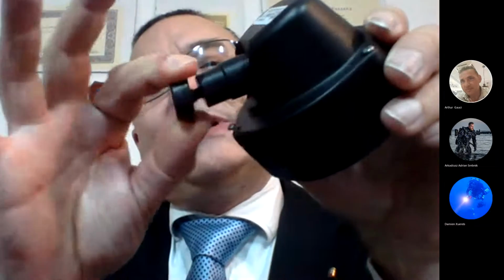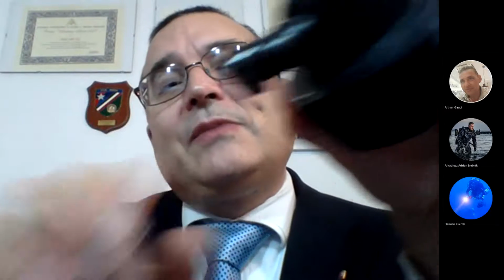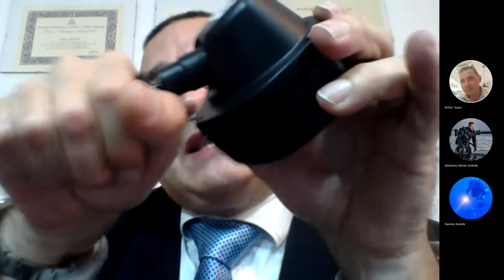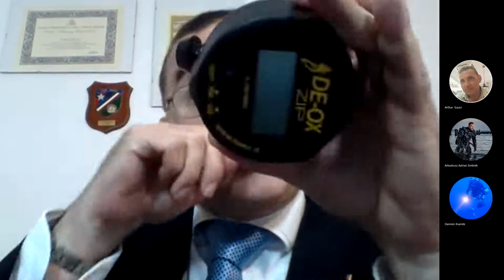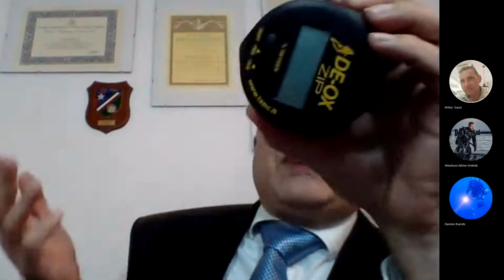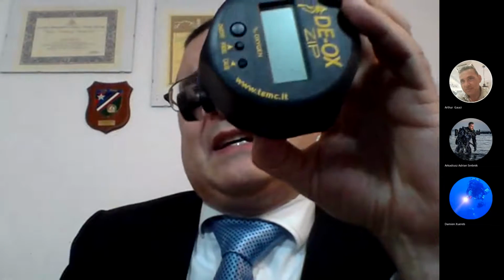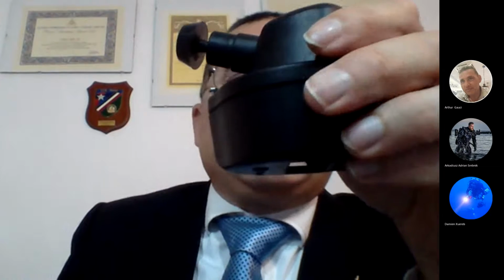So, okay, what is necessary for the analysis? Generally, the easiest way is to use the rubber cap. This is a rubber cap that you put on top of the sensing part of the sensor. You first turn on the cylinder very slowly, and then you put the analyzer on top, and then you do the analysis. This is the easiest, this is the fastest, what you will do 90% of the time, and for most applications it is the best way of doing the analysis.